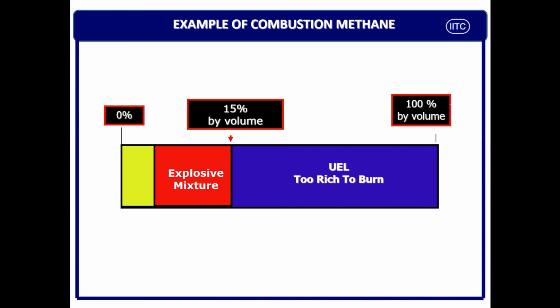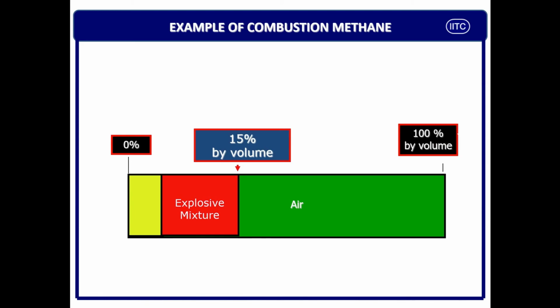Red means LEL starts. If you enter this red zone, the explosive mixture zone, which is between LEL and UEL, it can be explosive. And at the end point of the explosive mixture, the red legend before it comes to the blue, this is the UEL. This is the last point where there is a possibility of burn, ignition or explosion. Beyond the UEL, the gas is too rich to burn. Probably you may have more methane, but it will not burn. So this is how we understand the meaning of LEL and UEL.